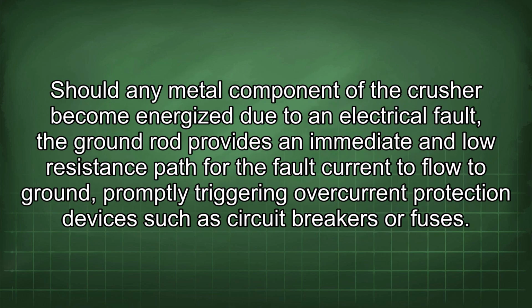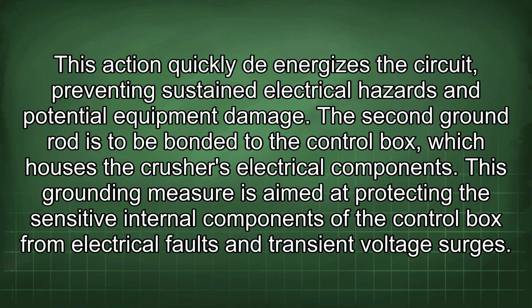Should any metal component of the crusher become energized due to an electrical fault, the ground rod provides an immediate and low-resistance path for the fault current to flow to ground, promptly triggering overcurrent protection devices such as circuit breakers or fuses. This action quickly de-energizes the circuit, preventing sustained electrical hazards and potential equipment damage.